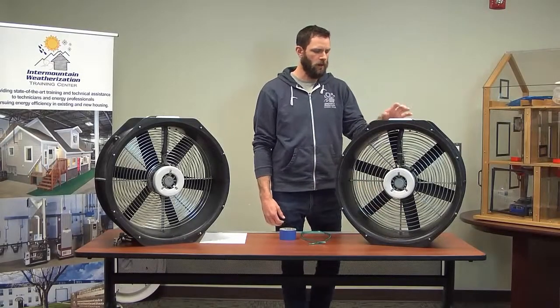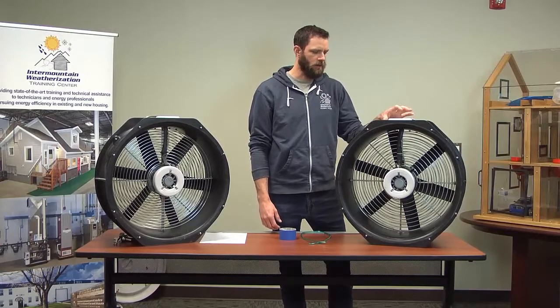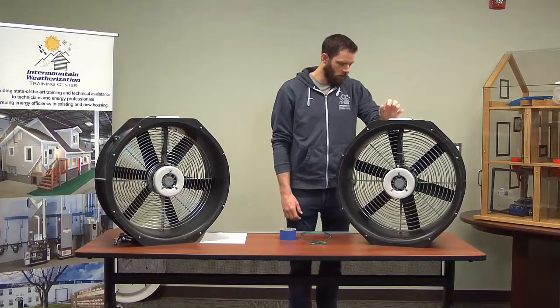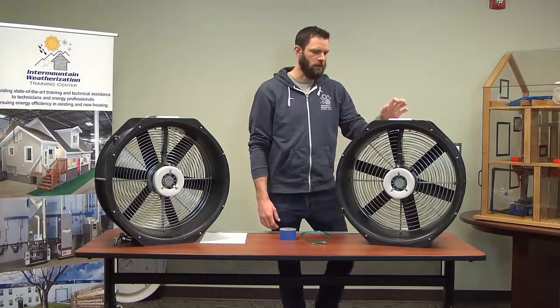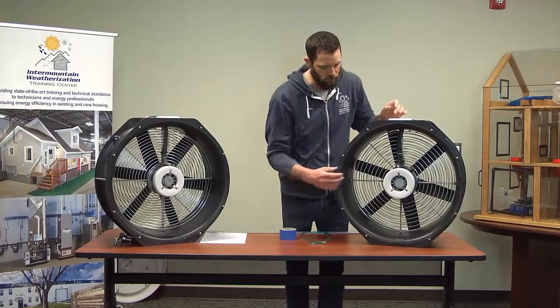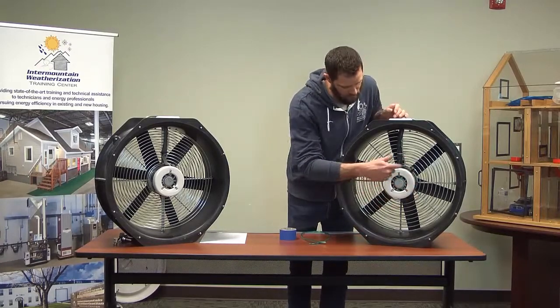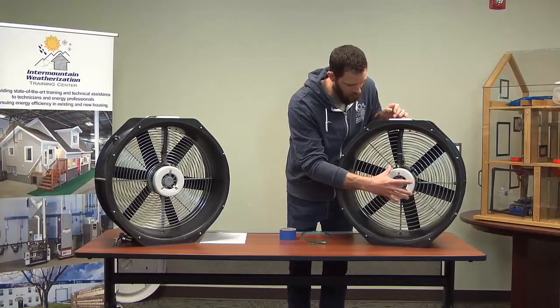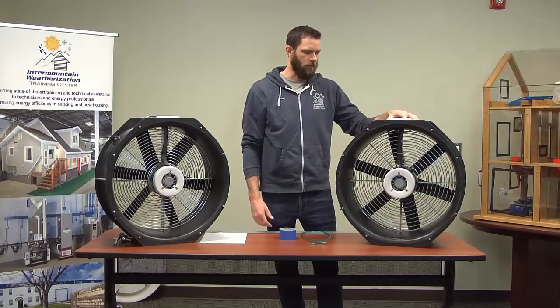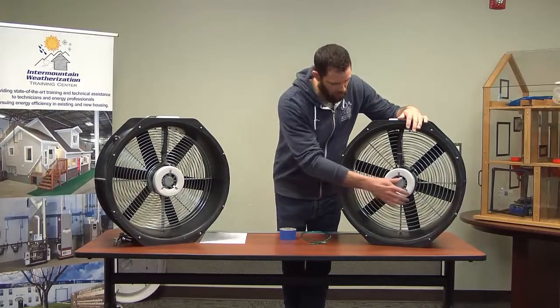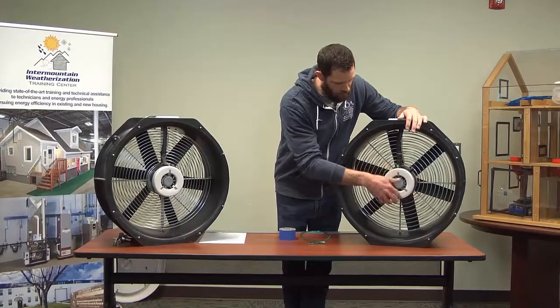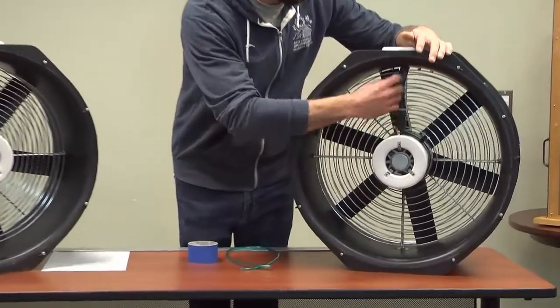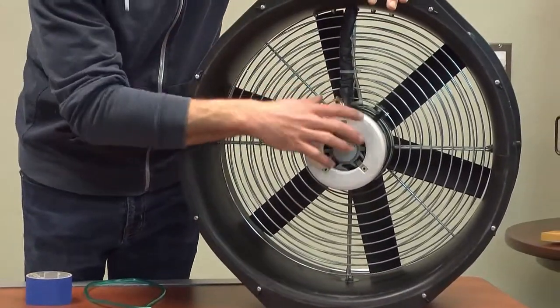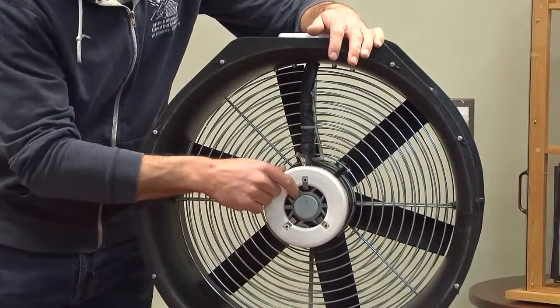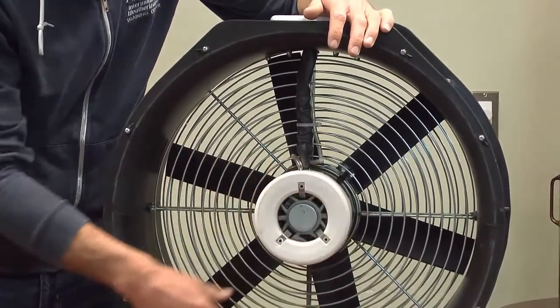So we're going to go over the procedure of field checking the Model 3 blower door. We're going to start by doing a leakage and damage test on the flow sensor, and that's this white cap here on the end of the motor. Basically what we're checking is that there's no damage to it or the hose that runs up to the flow port on top of the blower door, and also we're looking for any kind of cracks in the actual housing.